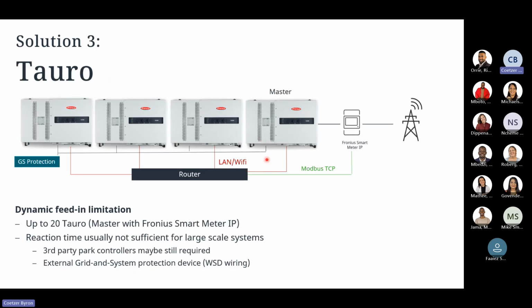Solution 3 is if the client has got multiple Tauro devices. So what we like to say is you can do up to 20 Tauro devices connected into a simple system with a Fronius smart meter IP. Again, this allows for us to do a system size of up to 2 megawatts effectively with just one simple master and simple smart meter connected to the system itself. So again, it's very similar. We'll have the master assigned where it'll have its smart meter IP communicating via Modbus TCP. And this master will then communicate via this TCP loop back to all the slaves in the configuration itself.